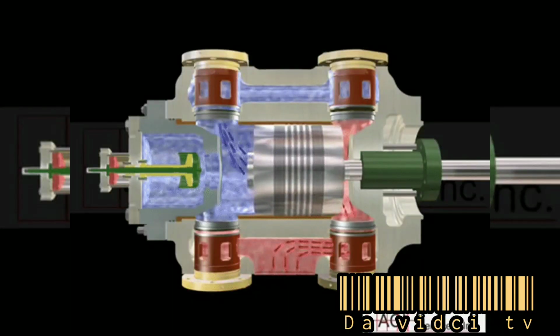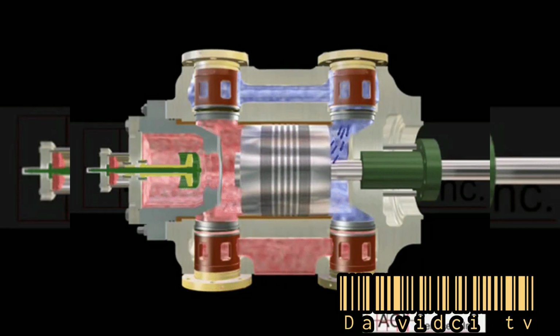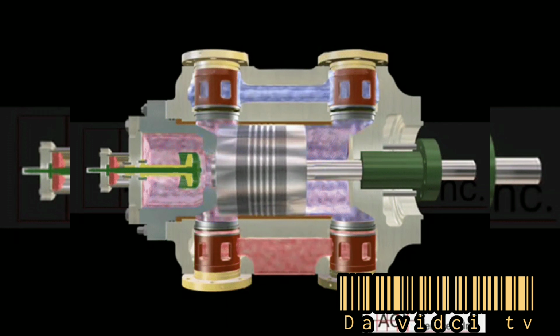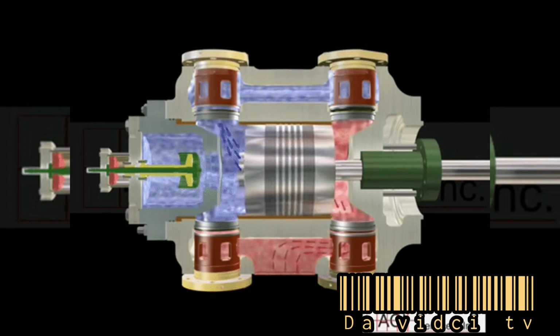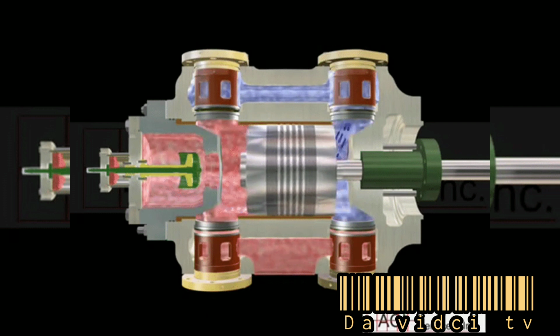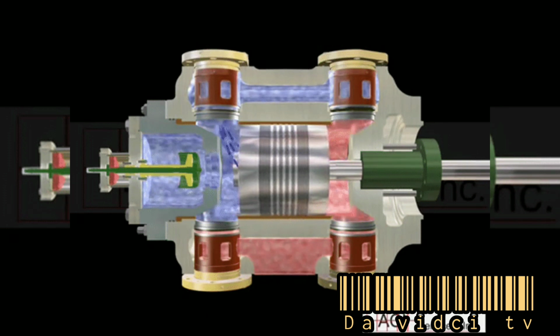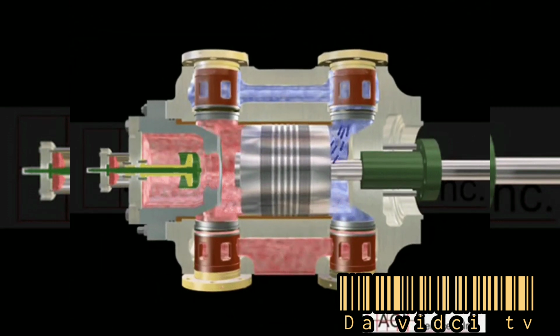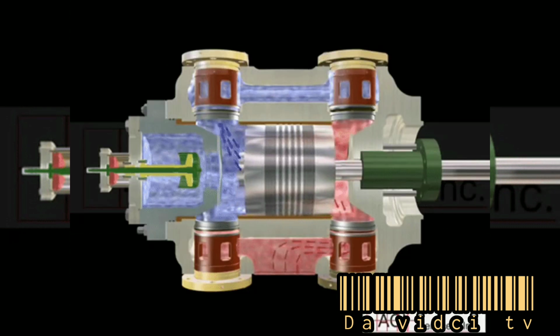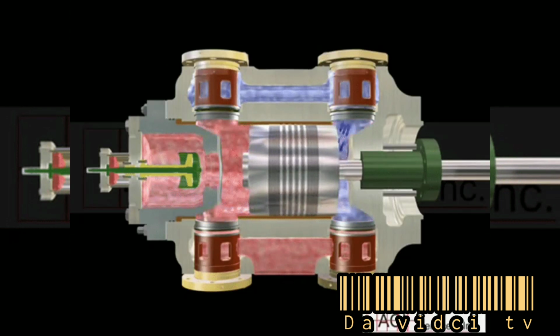The single-acting crosshead type in the small, double-acting, single-stage compressors are also driven in a similar manner. Larger, multi-stage, trunk-type compressors can be sized to operate at common motor speeds and therefore are direct coupled. The larger, crosshead, double-acting, multi-stage compressors present the most variations in drive arrangements.